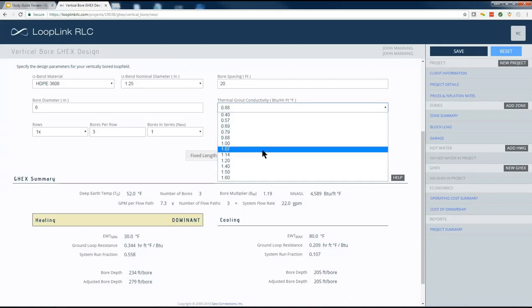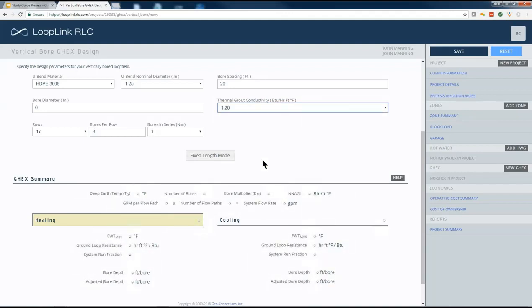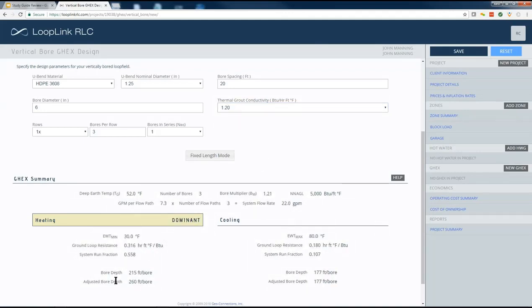Going from a 0.88 to a 1.2, one thing that you'll notice is the law of diminishing returns starts taking effect. Going from that 0.88 to the 1.2, you go from a 200-pound sand mix to a 400-pound sand mix, doubling the amount of sand that you put in the hole if that's the thermal additive that you're using. And you can see my ground loop design lengths actually didn't change nearly as much as they did by going from no sand to the 200-pound sand mix.